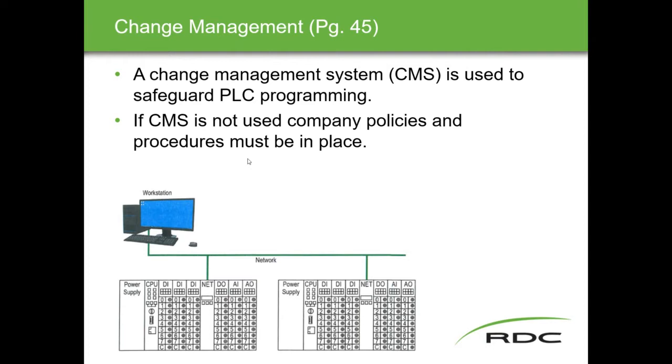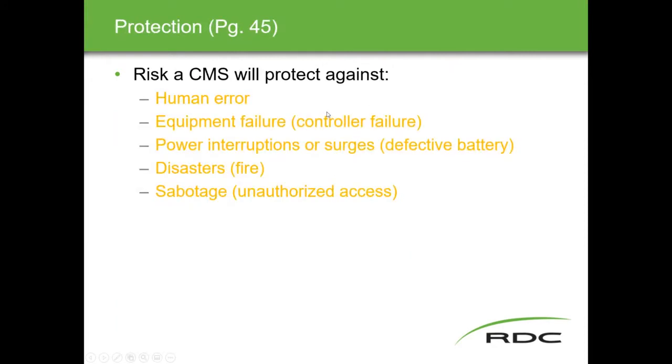When I worked for the city at the wastewater treatment plant, we had a binder next to the console that we used for programming. We would come in and say, okay, January 26th, Tyler sat down and in main routine, rung 42, I changed bit I4.0 from an XIO to an XIC, and I fill it in. It could be that simple, a book, it could be a spreadsheet, or it could be an actual piece of software that does it for you. What is the change? Change management systems are designed to protect against.